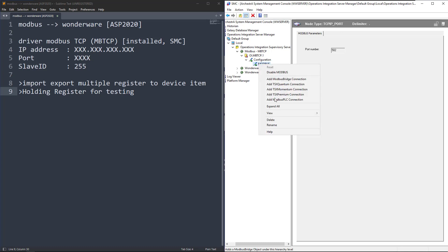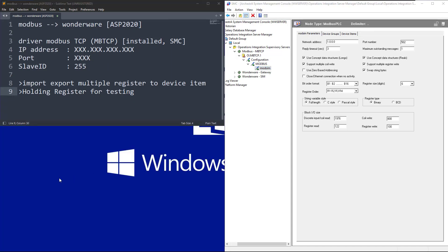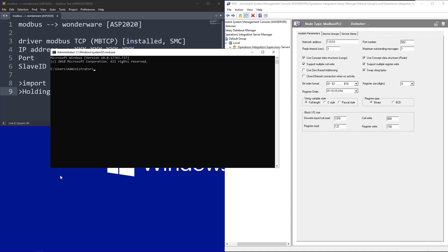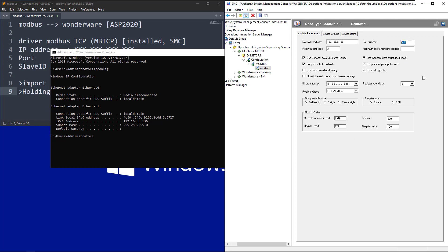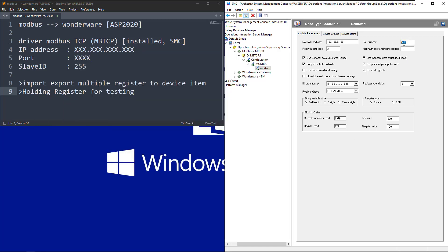I right-click again and add a Modbus PLC connection, because I will use ModSim. I'll name this 'modsim'. I'm going to use the localhost connection — my IP is here. I'll paste that in and use port 555. I open ModSim to see how it looks. For the connection we're going to use the Modbus DDE server and connect to port 555 on the Modbus simulator.